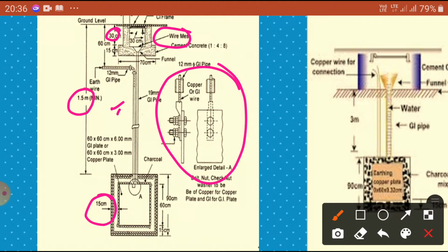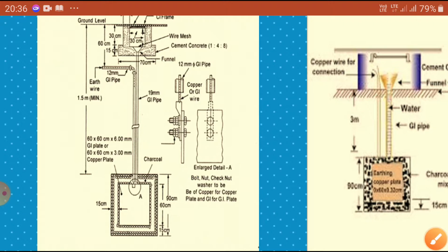So what is the procedure? You know the procedure. The copper plate is 60 centimeters by 60 centimeters, 3 mm thick, or sometimes we use a GI plate instead, but for a GI pipe or electrode, a 60 centimeter by 6 mm plate is used. A pit is dug to about 3 meters depth from ground level, or nearly 2.4 meters, and this depth is required for the filling. The earth plate is buried under the pit with its face vertical.